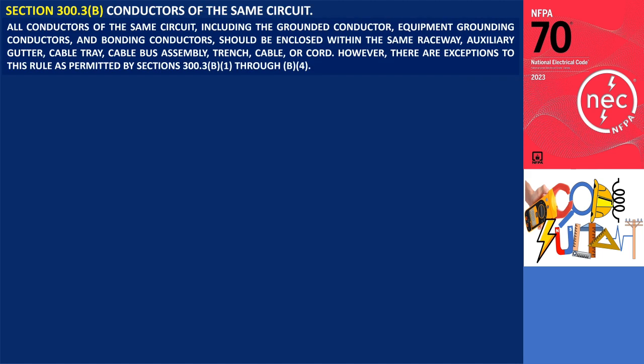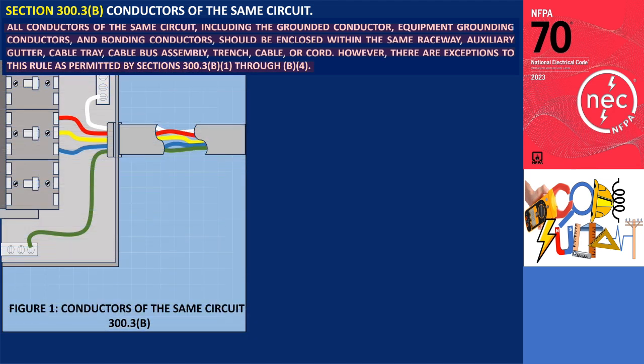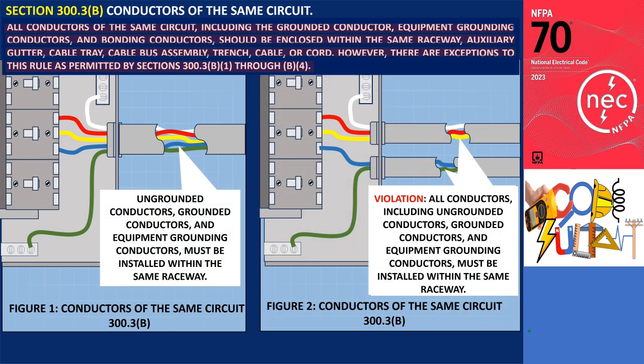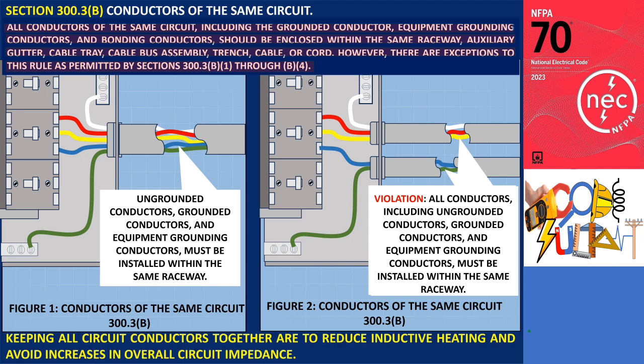Moving on to Section 300.3b, it states that all conductors of the same circuit, including the neutral and equipment grounding conductors, must be run in the same raceway, conduit body, auxiliary gutter, cable tray, cable bus assembly, trench, cable, or cord unless otherwise permitted in accordance with 300.3b1 through b4. Figure 1 serves as an example that complies with these rules, while Figure 2 represents an installation that violates Section 300.3b. The main reasons for keeping all circuit conductors together are to reduce inductive heating and avoid increases in overall circuit impedance.